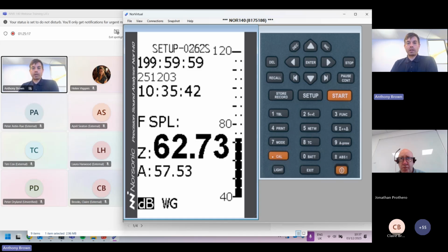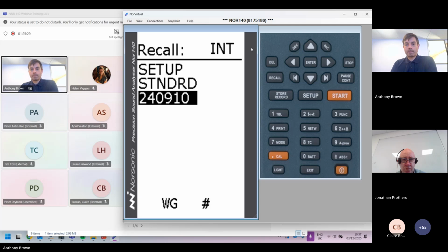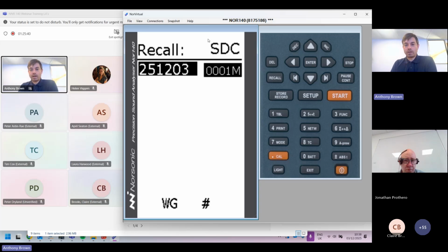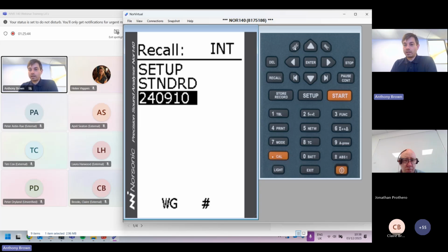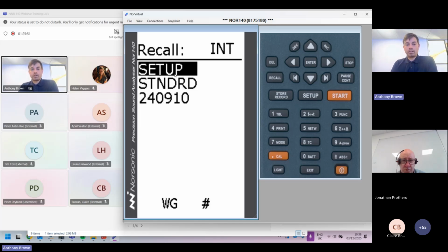So I press the store record key to get the setup file, which is 262. Let's say I've come to a new day and I want to load in those settings. I press the recall key, and you need to make sure at the top it says INT for internal, because that's where the settings are saved. And if it's not set to that, press the inc key until it says INT. So press this button, inc key, or the dec key, until it says INT for internal. And then you go up using the arrows to setup. So go to setup and press the arrow to the right to get a menu down the side here. And then I've got my number 262 from today that I can press enter on, and it will load those settings that I've just done and saved today.